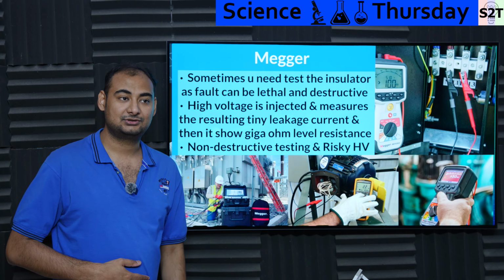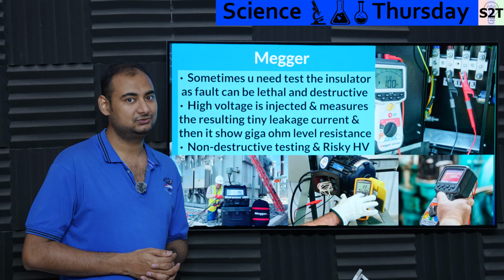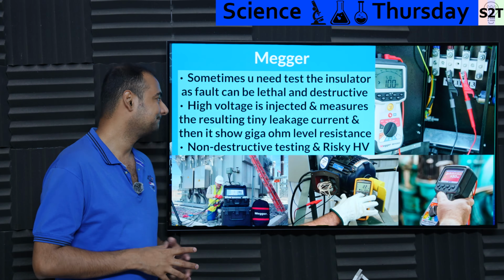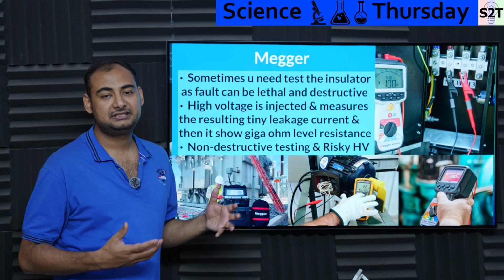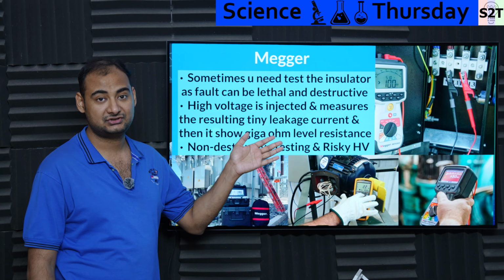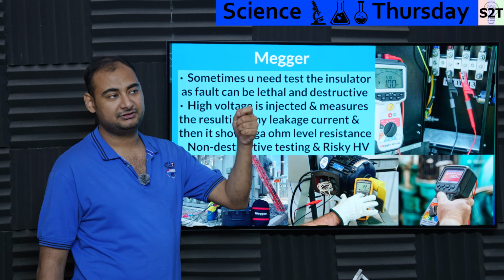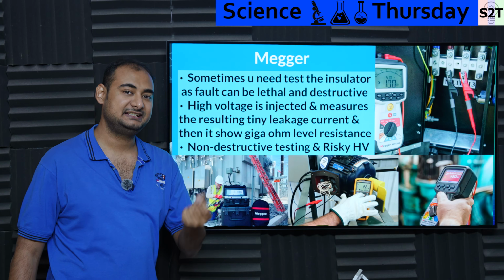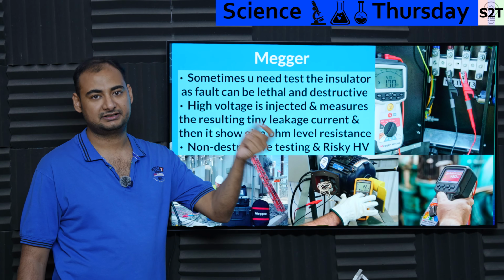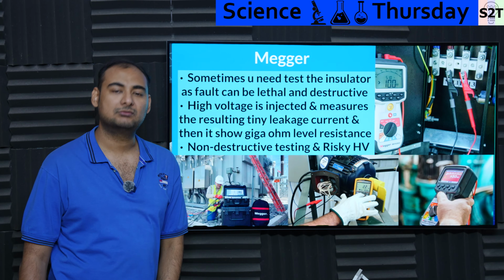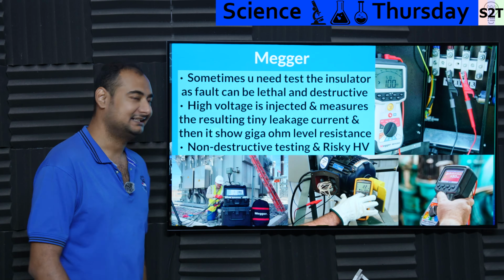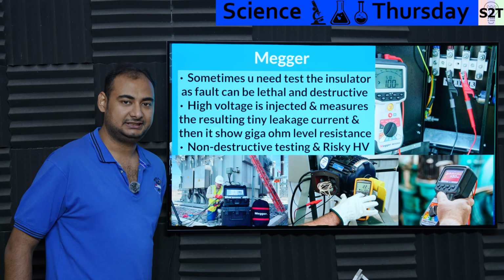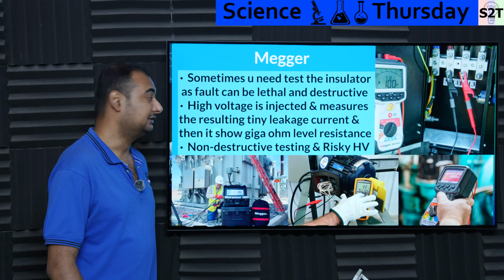But whenever you're talking about insulation, they do care about voltage, because that's what breaks. The penalty of insulation failure could be lethal and destructive. For example, imagine a failure where the heating element, which is AC mains power, leaks current directly into your water, and the whole water gets electrolyzed. That's lethal, an electrocution hazard, a serious one. And not to mention destructive.